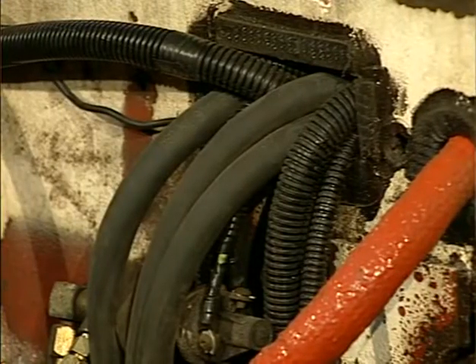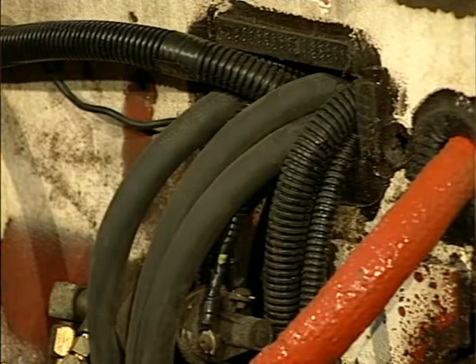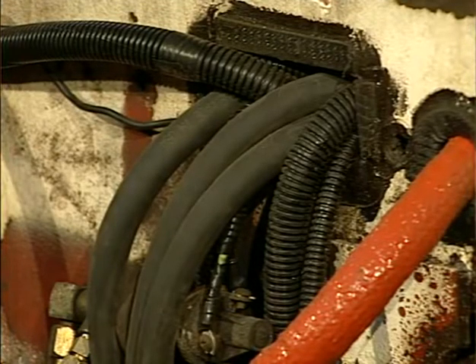Here we see that the electrical wiring must have adequate mechanical protection to prevent damage to the cable. But in addition to mechanical protection, wiring must be separated from sharp edges and corners where there's a possibility of damaging the wires and cables.